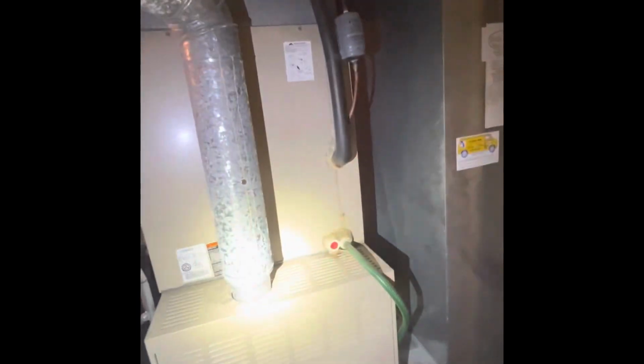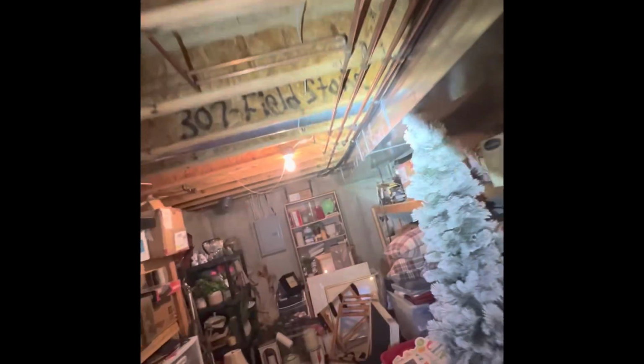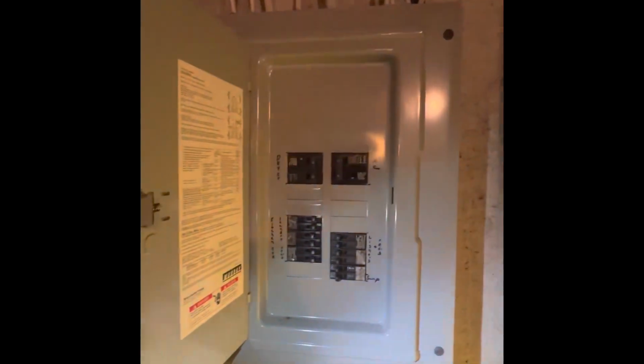We do have enough height for a 6-inch base to put that on and get our wraparound built back to it. We'll probably resize our return drop so that we can get that wraparound built. And as far as access, our line set runs from this closet all along this main trunk and then pokes to our outside. Our electrical panel is on a double pole 50, I believe. Yeah, double pole 50.